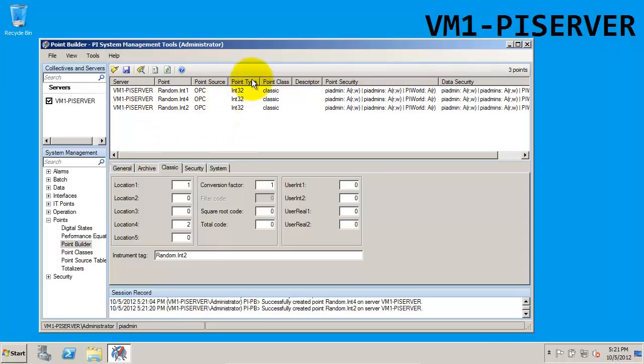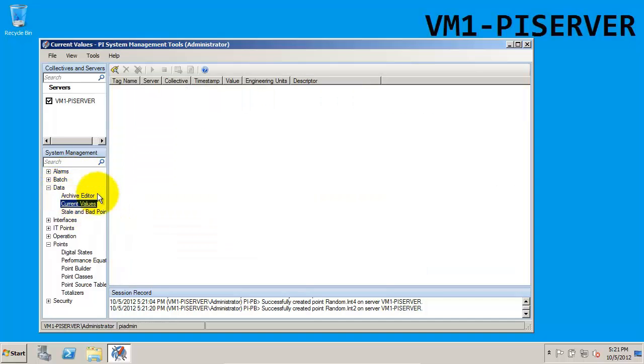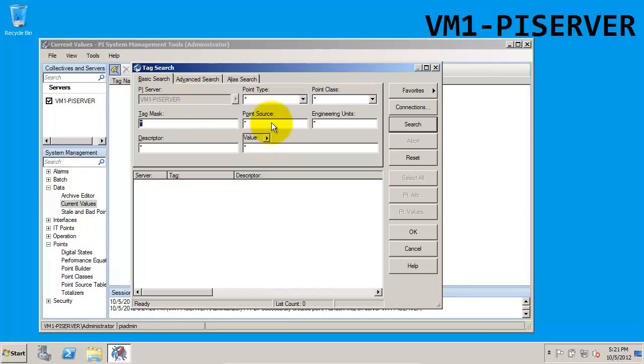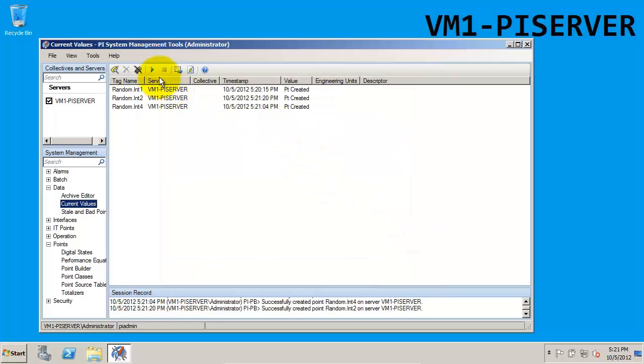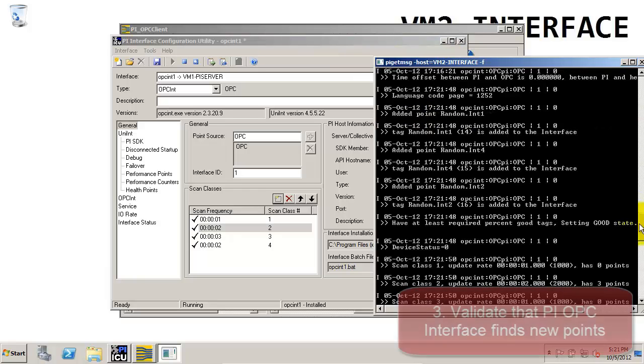Now that we've created our three OPC tags, let's check to see that we're getting data for them. If we go to current values, we can do a quick search by typing in OPC as the point source. There are our three tags — we'll select all of them. You'll notice that the value shows point created. Since they were just created, it may take up to 2 minutes for the interface to pick up the new points. If we go back to the OPC interface node and check the message log, it will show once the new points have been picked up.